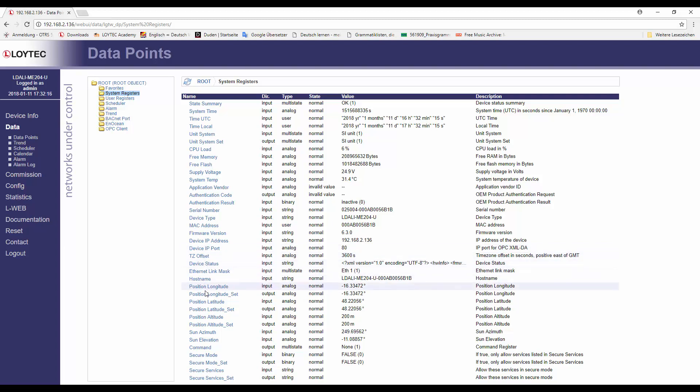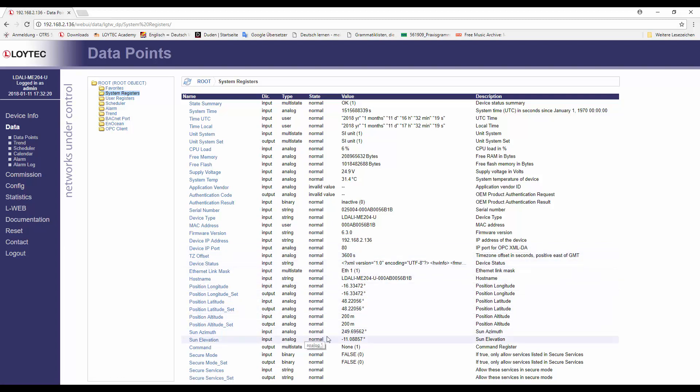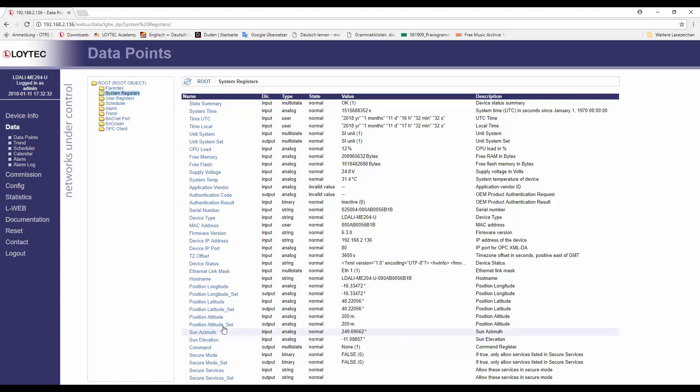The LDALI has now two new system registers for sun azimuth and elevation, which are calculated based on the current daytime and the geographical location. These system registers can be used for the corresponding inputs of the sun light controller application to control the position and the rotation of a sun blind according to the sun azimuth and elevation.